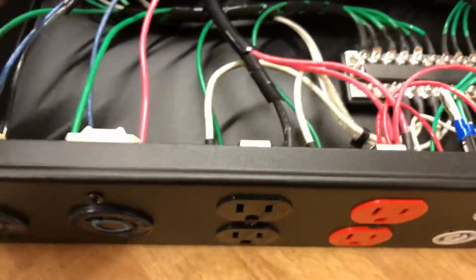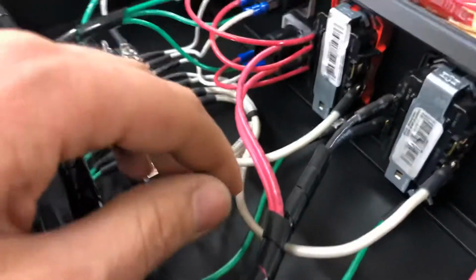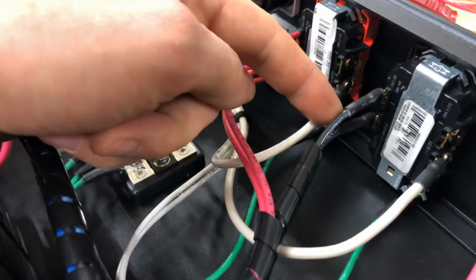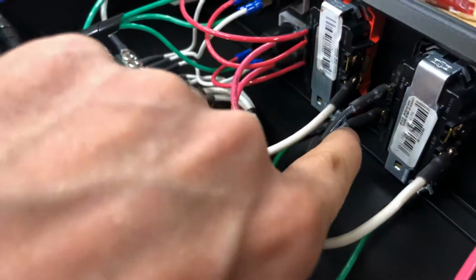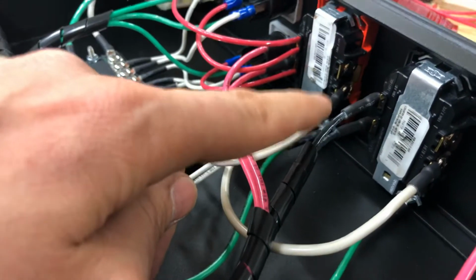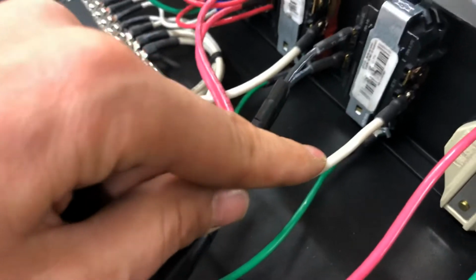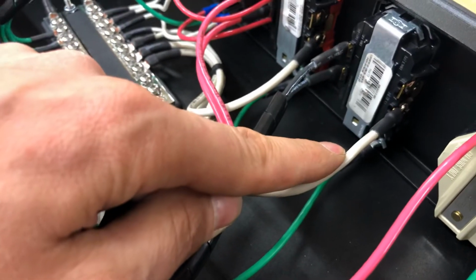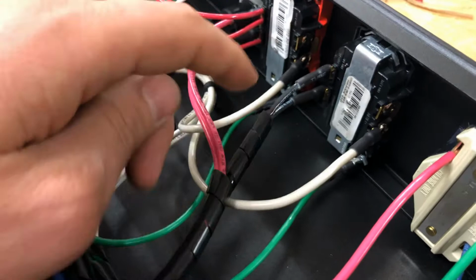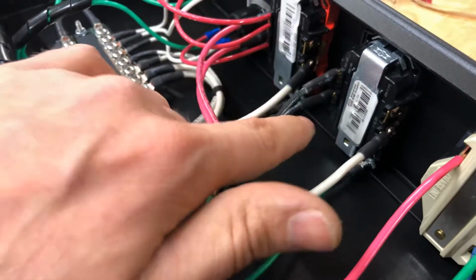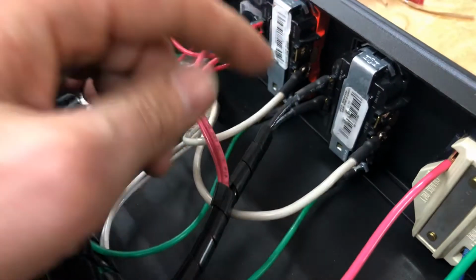On these outlets here on the back, I ended up splitting them, like I said, so each one has a 20 amp feed, but they're on the same phase and they share a common neutral. So I upsized the neutral to 10 gauge here, because these are not across multiple phases.